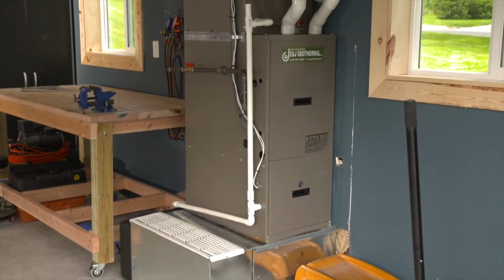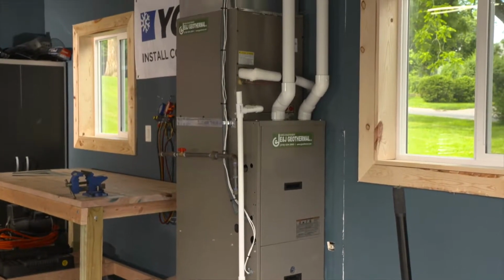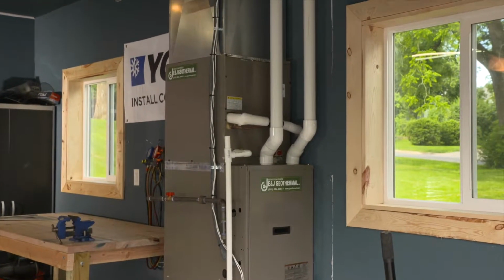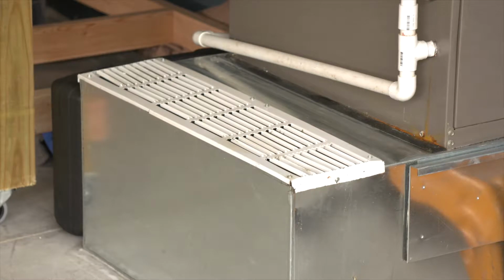On the furnace side, there's two types. You have your 80% models that do not have a condensate, similar to using a hanging heater. Then you have high efficiency models near 95, 96, even 98% efficient. But because they have a condensate, the garage would need to be kept about 40 to 50 degrees year round, otherwise the condensate has a chance to freeze.